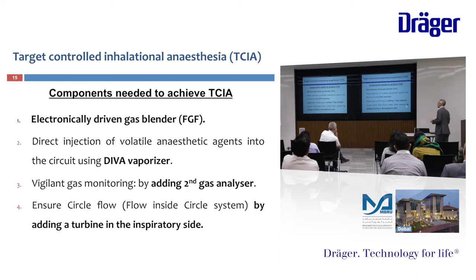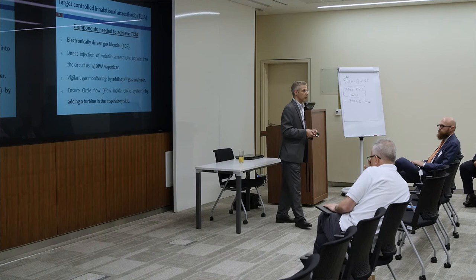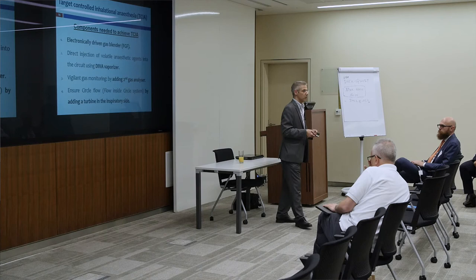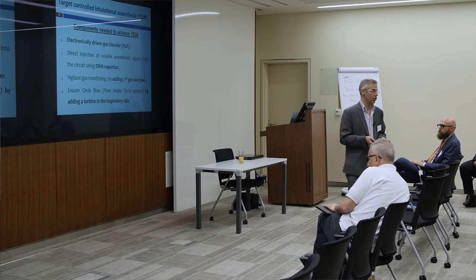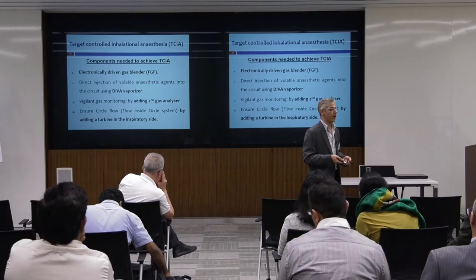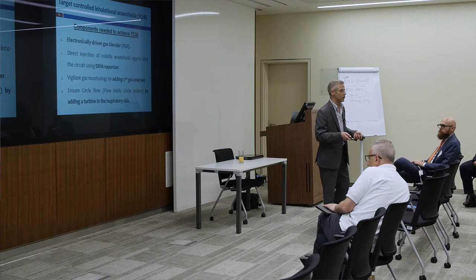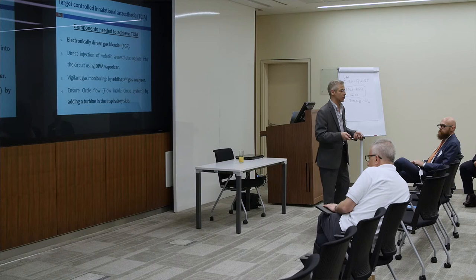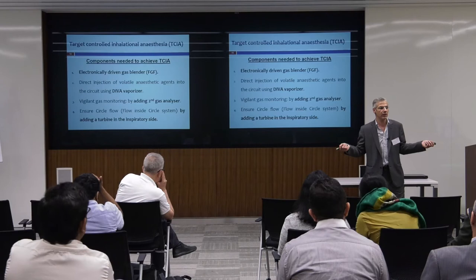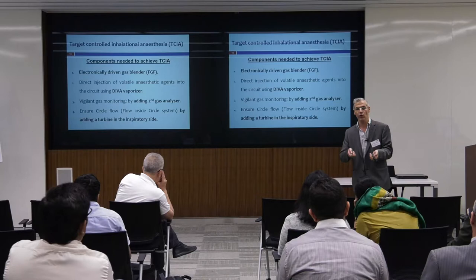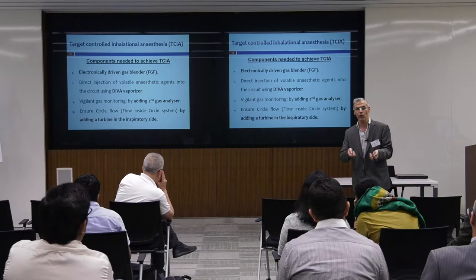We need to ensure circle flow inside the circle system by adding a turbine on the inspiratory side. As our Draeger team mentioned during the symposium, it is the only anesthesia machine by Draeger having a turbine, and it can supply up to 250 liters per minute. It's controlled automatically and we never reach this limit — it's just like having a Ferrari that can reach 360 km/h but you drive at 140 or 160. That's just an option available. It can give all the advantages of an ICU ventilator.